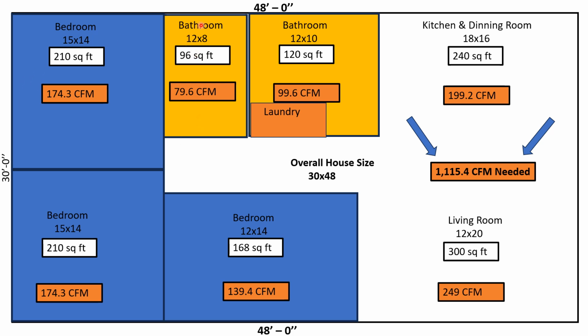Same thing here. I can put a 6 inch in this half bath, I do believe, but a 6 inch, according to ASHRAE, with a 0.50 is going to carry right at 75. So a 6 inch is going to be too small. I'm going to have to put in a 7 inch and then damper it down. And on that bedroom, I could use a 7 inch and damper that one down as well. Here we have 139, so this one's going to have to be an 8 inch and dampered back. This one I have two options: I could do a 7 and a 6. And here in my living room, of course, I would want multiple options, so we may do one here, one here, and in the kitchen, depending on how the layout is. That's something you can actually figure up yourself. But here's the number I wanted you to look at, where the arrows are.